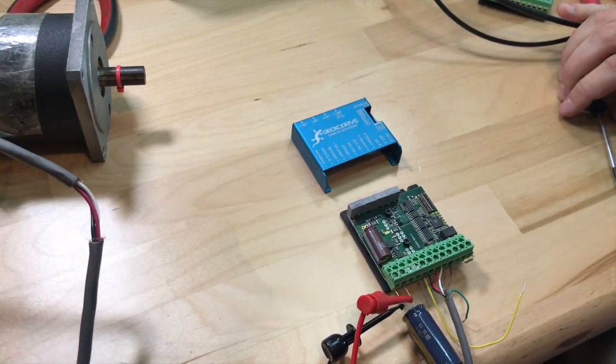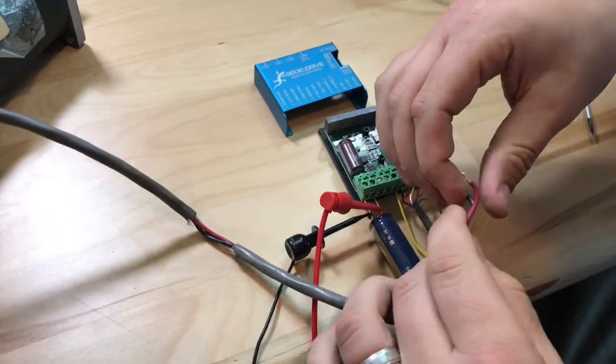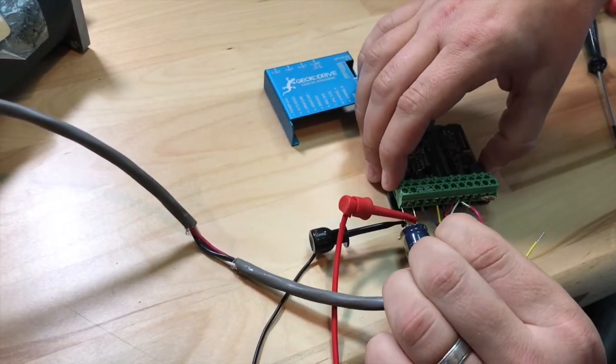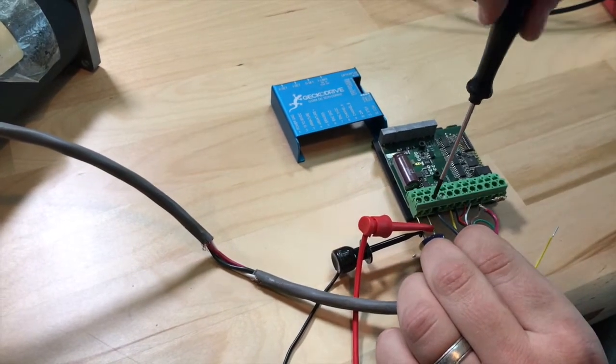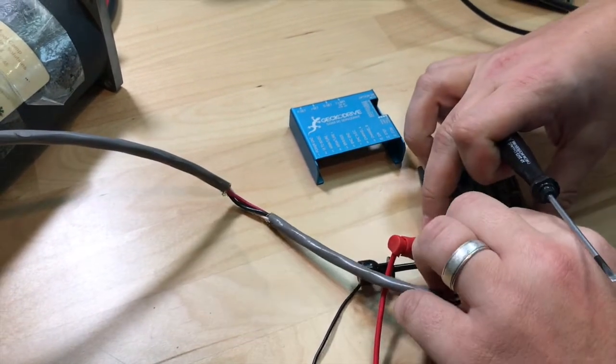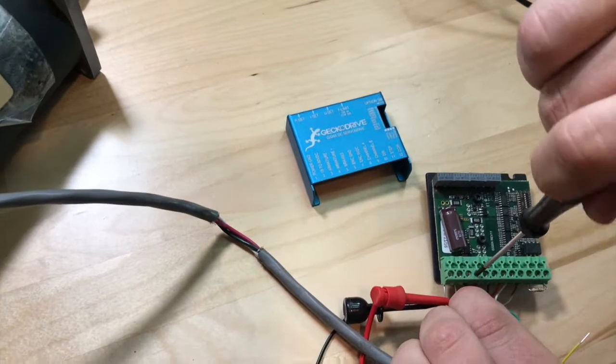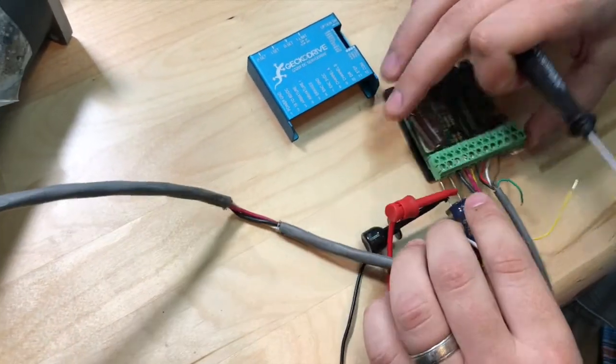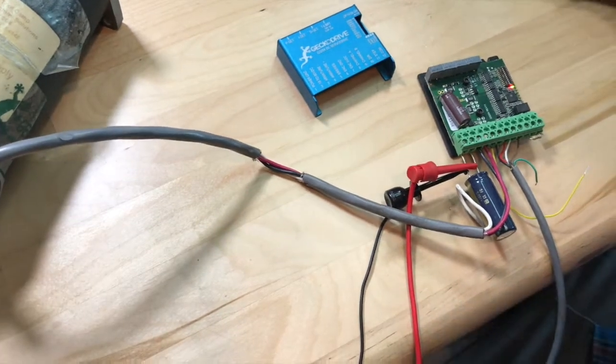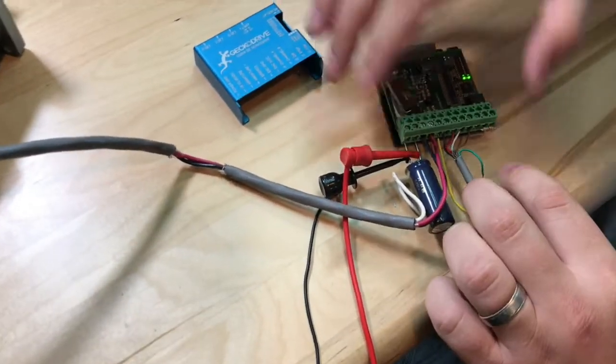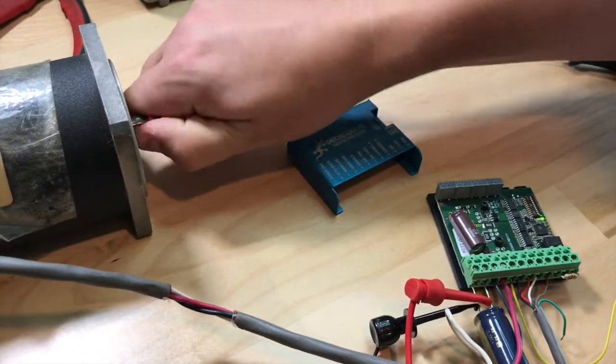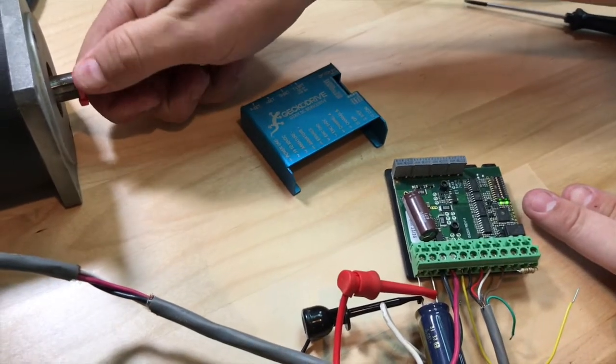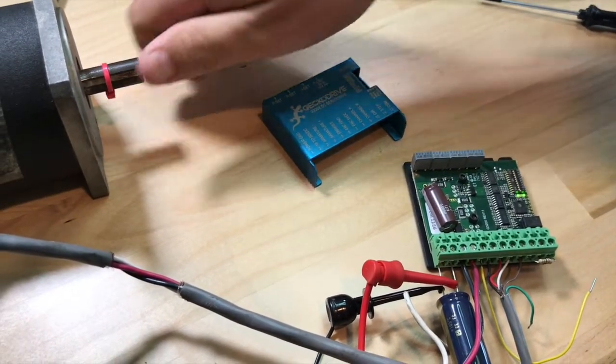So let's turn power off and now let's connect the motor. This is just to make sure that the motor is receiving power. We'll put armature negative into terminal 3 and armature positive into terminal 4. Now we will apply power, reset the drive. And now I'm going to try to turn the shaft by hand and it'll resist. You see the green LED go out as I do that. It's trying to maintain position, which is a good sign.